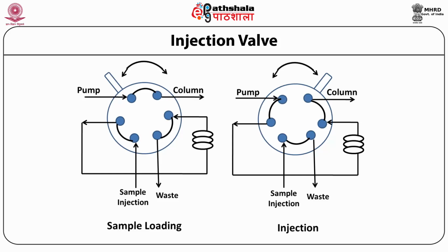The sample injection into the HPLC system is very important in analytical processes, and the quality and flexibility of the sample injection valve are therefore very important for reproducibility of data. Valve injection allows rapid, reproducible and operator-independent delivery of the sample. It also offers the advantage of injection of a wide range of sample volumes, ranging from about 60 nanoliters up to several milliliters, at pressures up to 7000 psi with negligible errors of less than 0.2%.